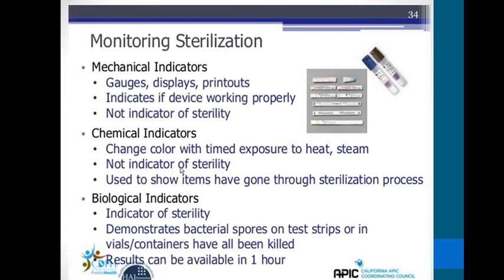So in summary, there are three methods: mechanical indicators, which are not an indicator of sterility; chemical (process) indicators, which are also not an indicator of sterility; and the biological indicator, which is the only method that demonstrates sterility by showing that bacterial spores on test strips or in vial containers have been killed. Results are available in one hour.